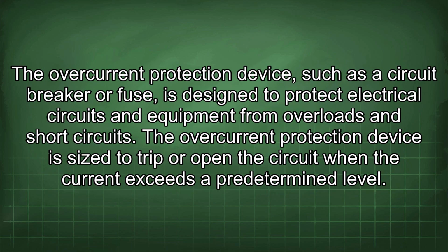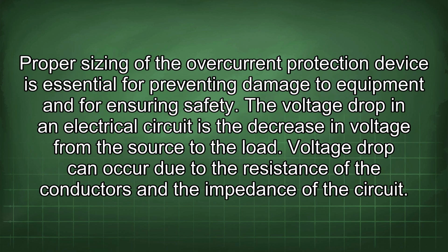The overcurrent protection device, such as a circuit breaker or fuse, is designed to protect electrical circuits and equipment from overloads and short circuits. The overcurrent protection device is sized to trip or open the circuit when the current exceeds a predetermined level. Proper sizing of the overcurrent protection device is essential for preventing damage to equipment and for ensuring safety.